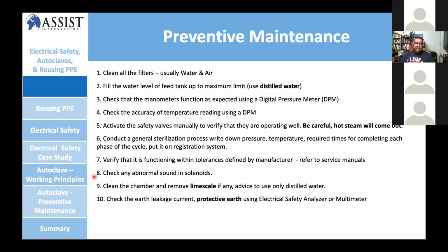If there's a leak on the heating element, you need to change it, because it's going to trip the system and cause a power failure. When you clean the lime scale, clean it properly and wash it properly. Use plenty of water to remove all the lime scale from the copper tubing, to make sure there's no blockage on your solenoid valve. Sometimes the solenoid valve doesn't perform properly due to this dirt. So make sure you remove the lime scale on the hot water boiler and everything.